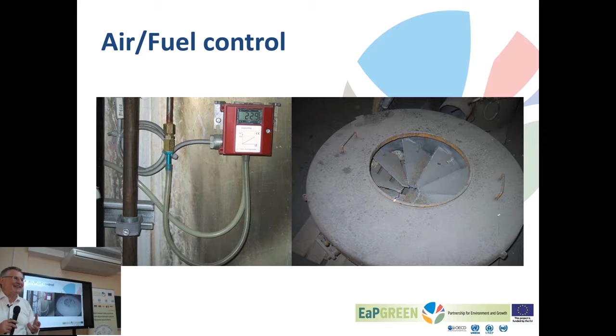It's not only about the nice equipment, the sensor, the controller, the frequency controller on the ventilator, but it's also about maintenance. And it's about awareness, because an operator should have recognized long before that actually the indicator was faulty and probably the control was not working. So technology cannot replace well-trained operators which are well aware of what they are doing.